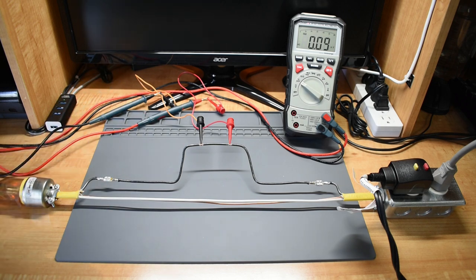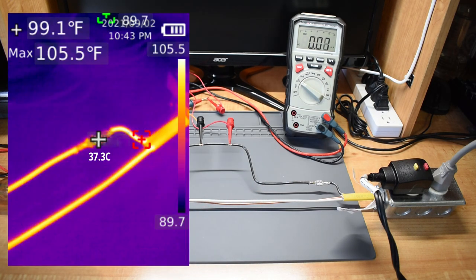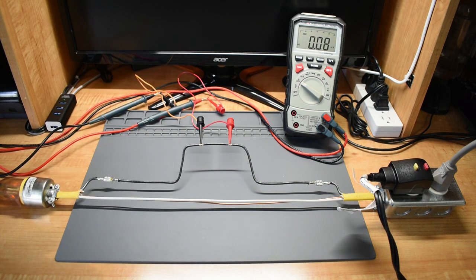Okay, the test is complete, 4.4 millivolts, pretty stable throughout the whole time of fifteen minutes. Deduct 0.05, that leaves 4.35. Right here is the temperature of the spot between the probes. You can also see the temperature of the soldered connections stayed as cool as the wire.